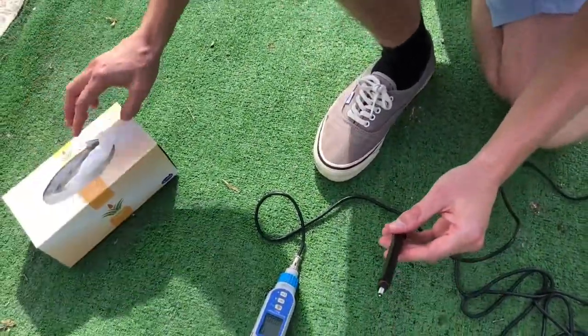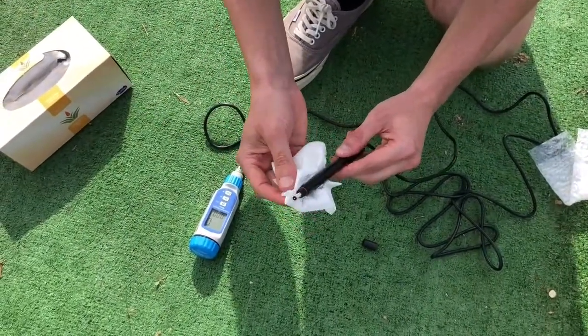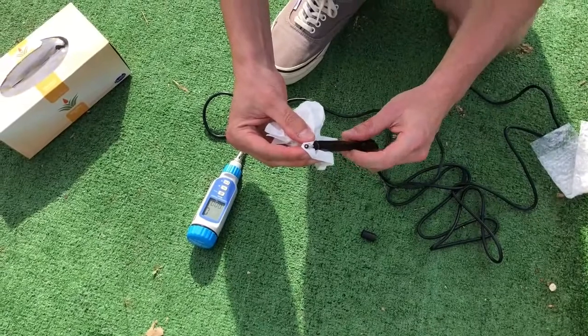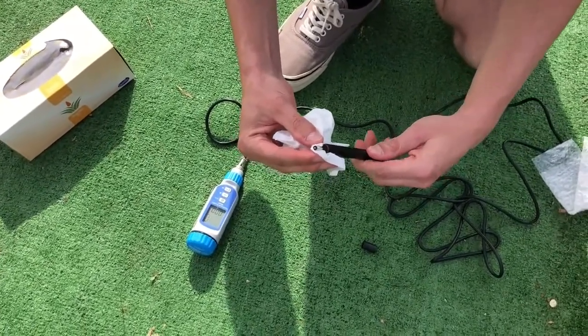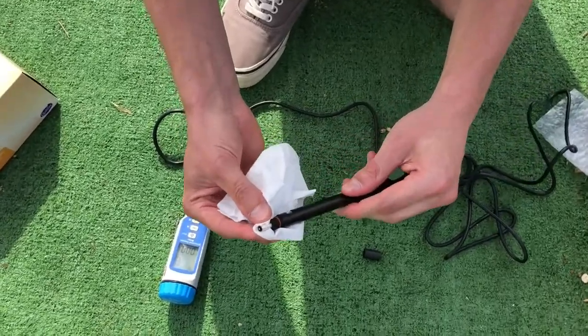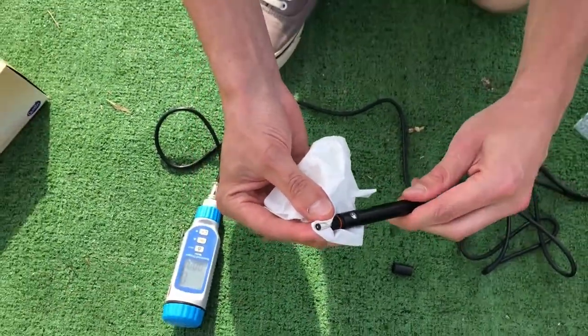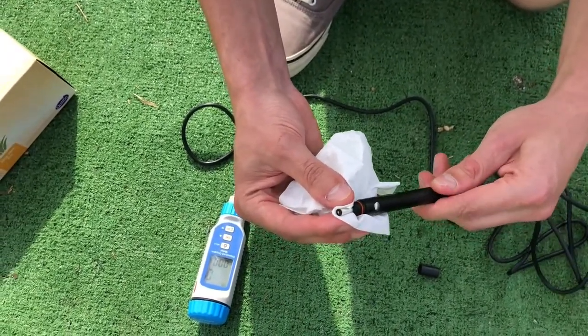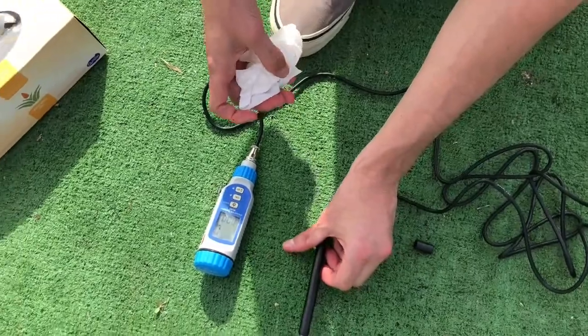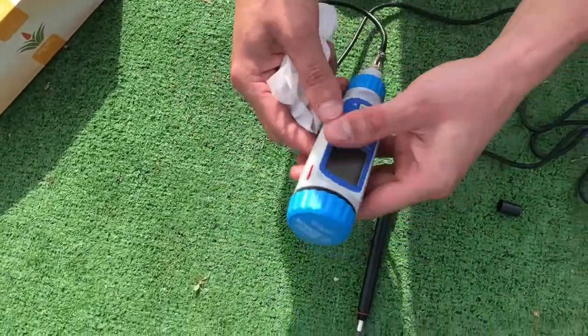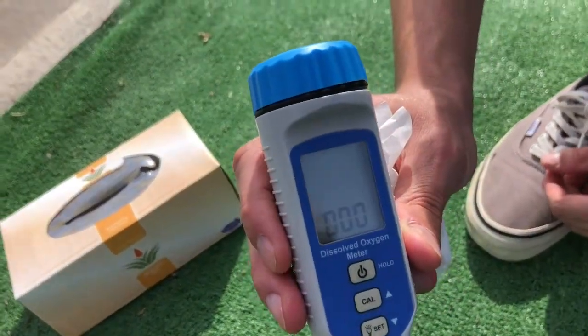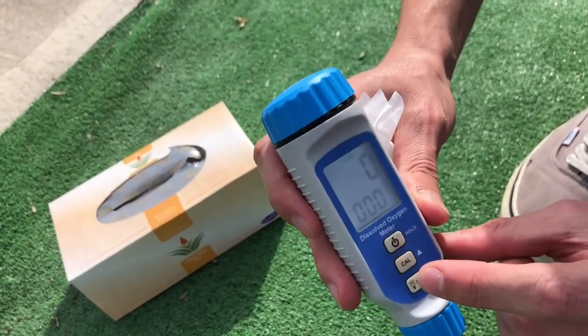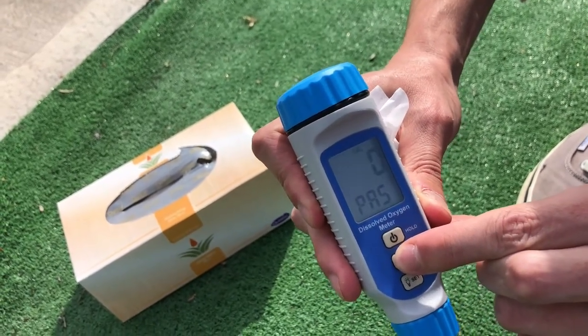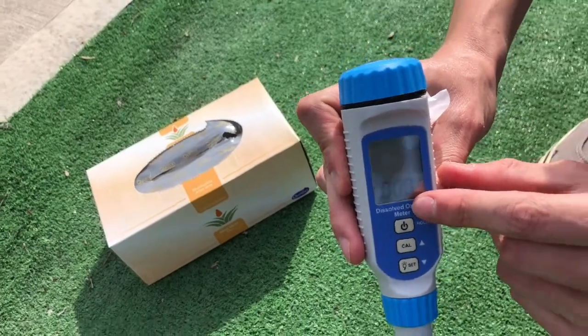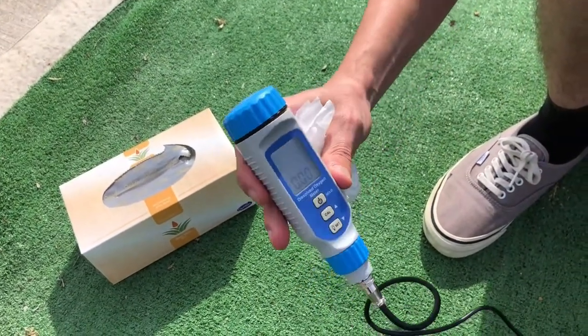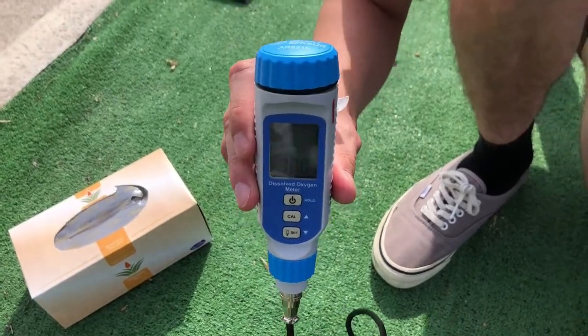So we use tissues just to very carefully dry the electrode that the probe's attached to, the metal electrode there. And as you can see, now that it's dry, we have a reading of 0. So in order to compute that into the meter, we just press cal, and you can see it just came up there with a PAS or pass, which meant that the 0 reading was recorded for the calibration.